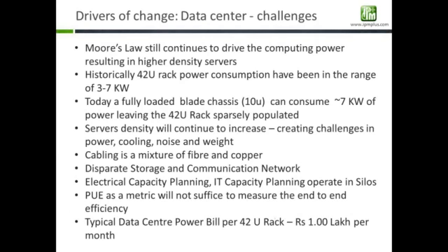Increasing the density of servers in the rack has a big impact because electrical cables were laid long back. You can't easily go and change all these back-end cables, generators, distribution panels. Second, you need to provide more and more cooling. Whatever power the server consumes, you need an equal amount of power to cool these high-end servers. So cooling is a big challenge today.